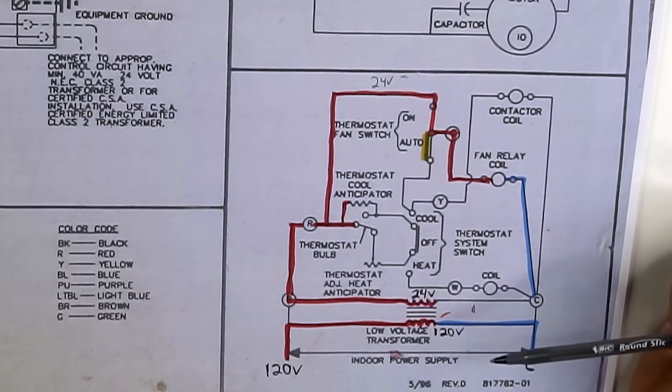I'm not going to go into the science of exactly how this works — it's a pretty simple control board that basically delays the start of the compressor by about five minutes until it closes back up and allows the power to go through. When the thermostat is calling for cooling, Y gets 24 volts, and there's a wire nut with two paths: one going through all these switches, or one going straight to the contactor coil. Note 14 says this wire is not present if HPS, LPS, DTS, or CTD are used. So if your unit has any one of these switches or the control board, this bypass wire will not be present.